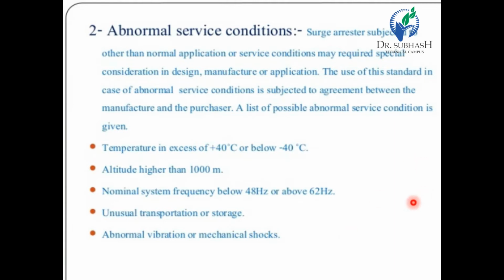Now abnormal service conditions. Surge arrestor subjected to other than normal application or service conditions may require special consideration in design, manufacture or application. The use of this standard in case of abnormal service conditions is subject to agreement between the manufacturer and the purchaser. A list of possible abnormal service conditions is given. If the temperature exceeds +40 degrees or is below -40 degrees, then it will be considered as abnormal condition.